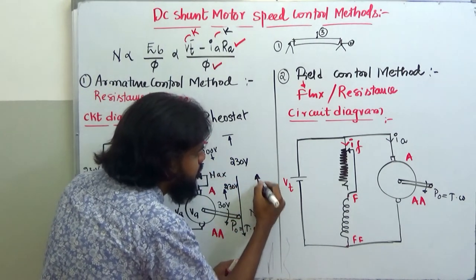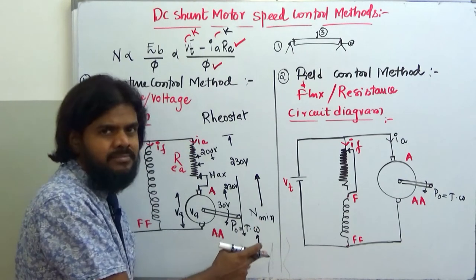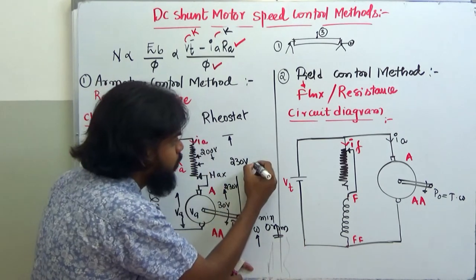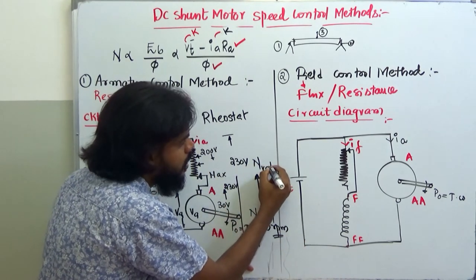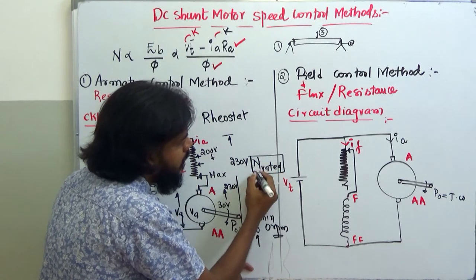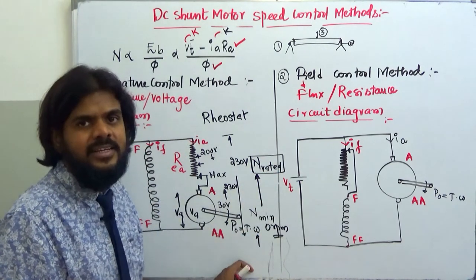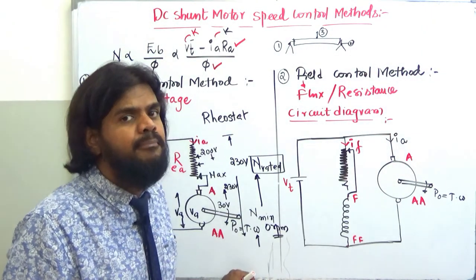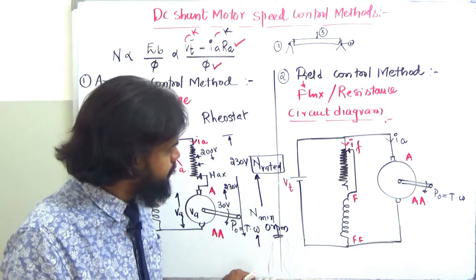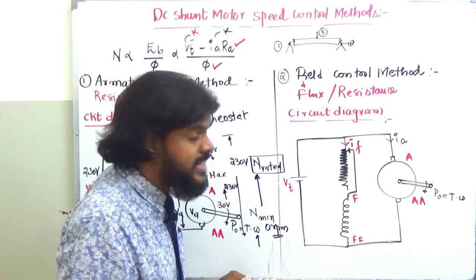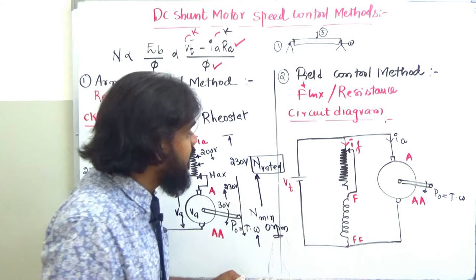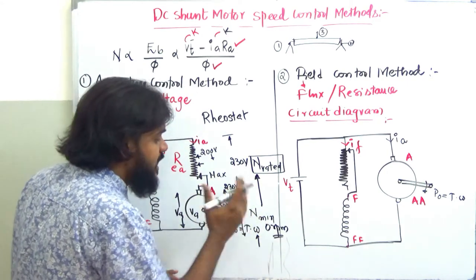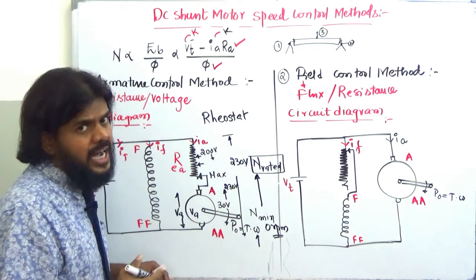As the armature resistance is cut down to zero, the voltage across the armature rises from zero up to the rated supply of 230 V, and thereby the speed rises from its minimum — approximately zero rpm — up to the rated rpm.